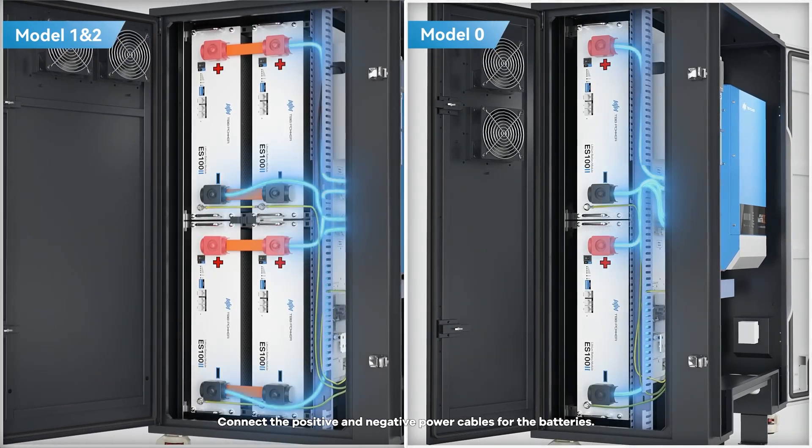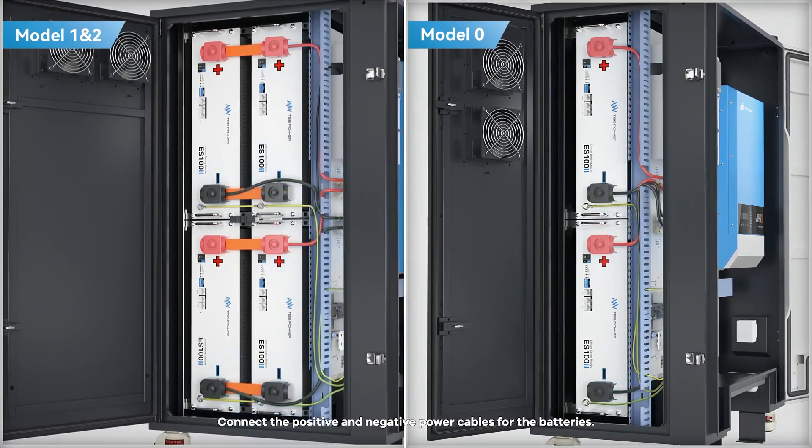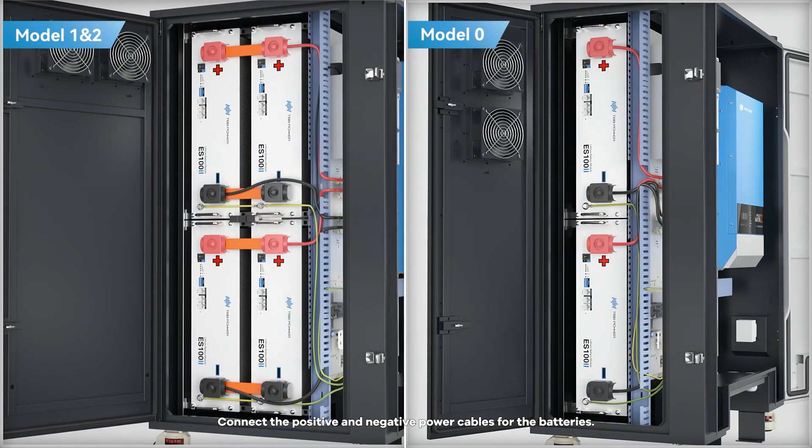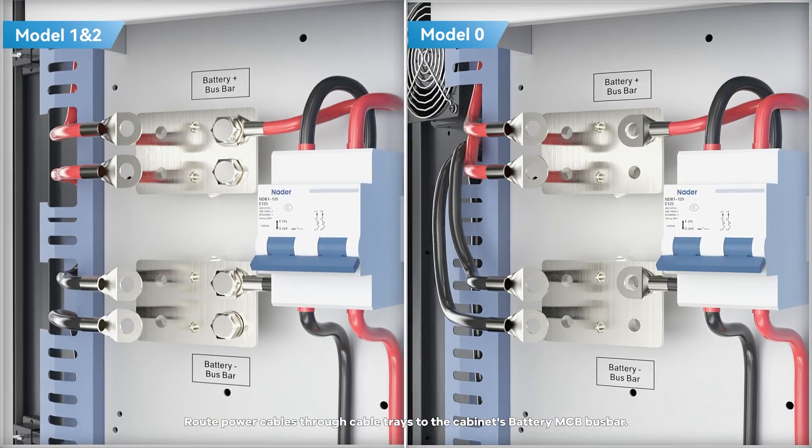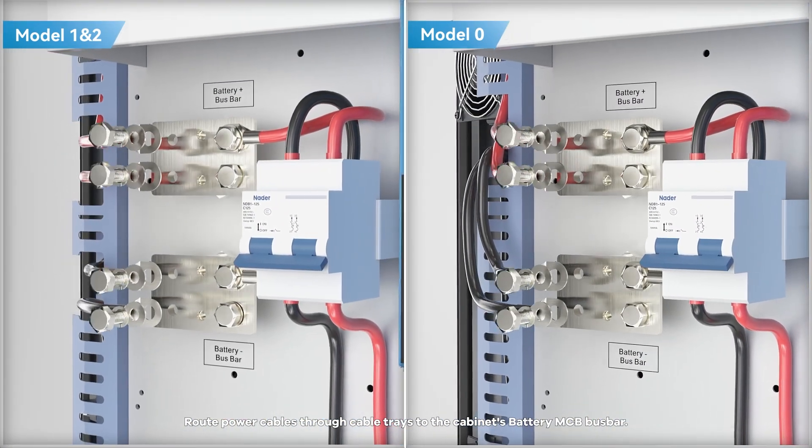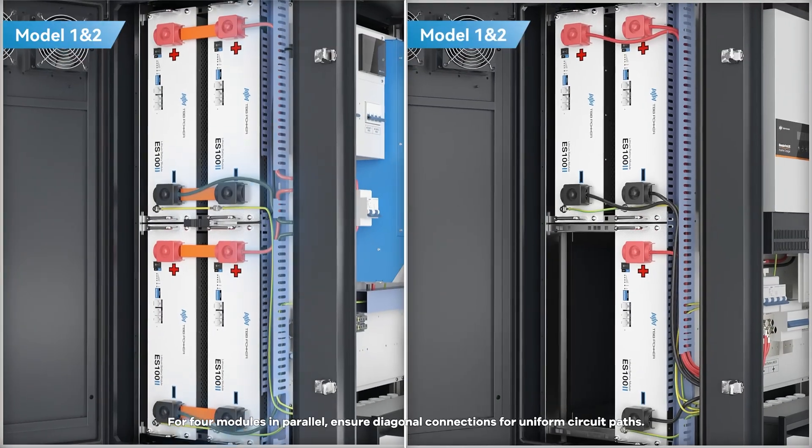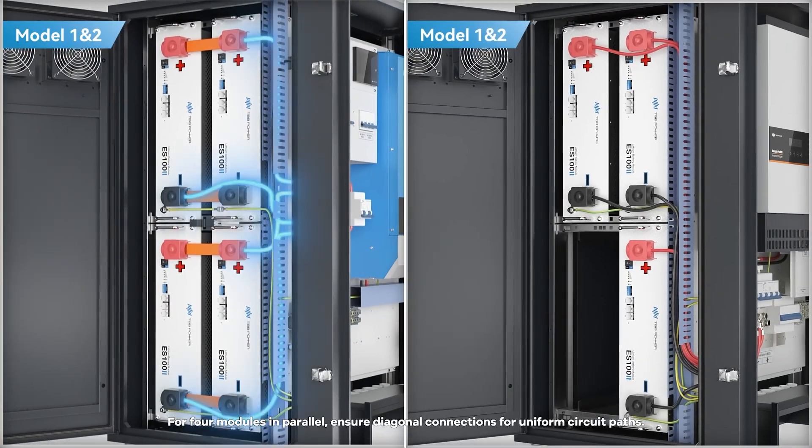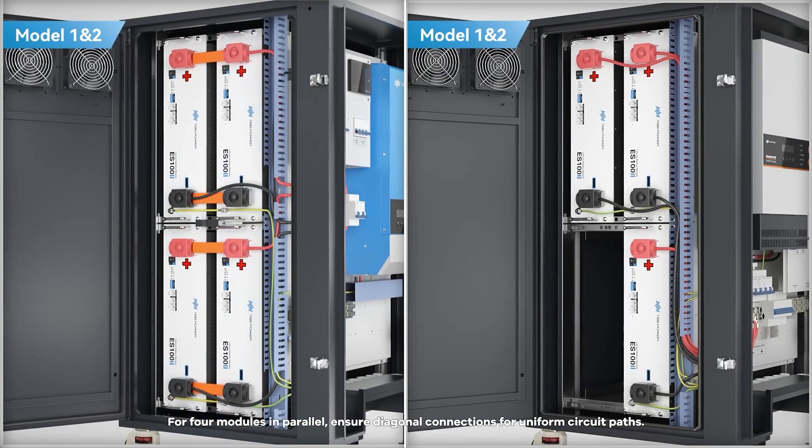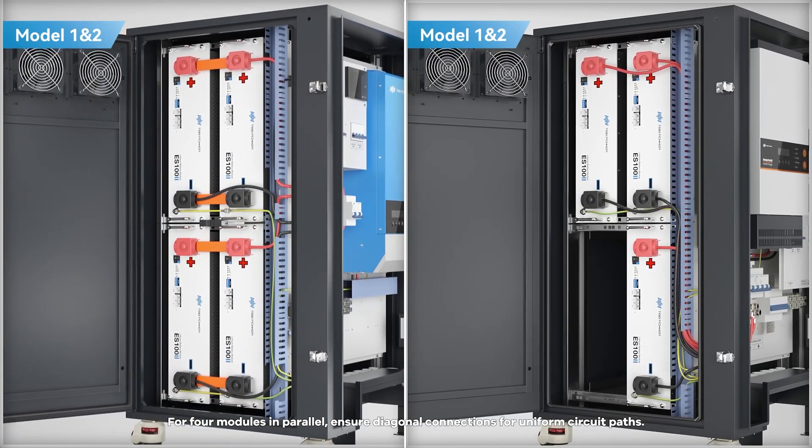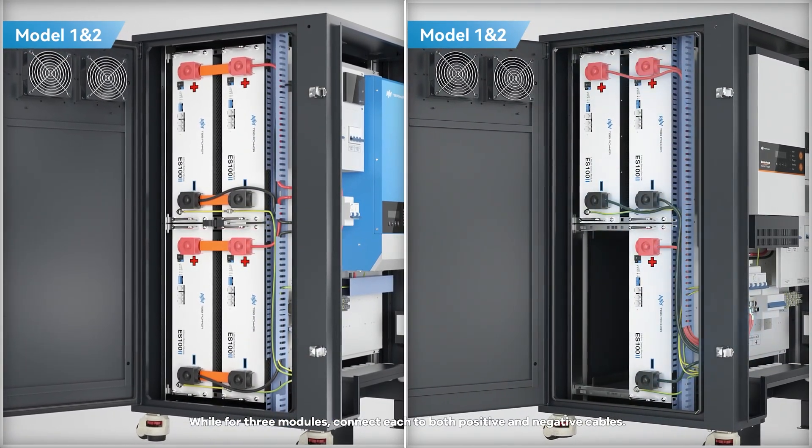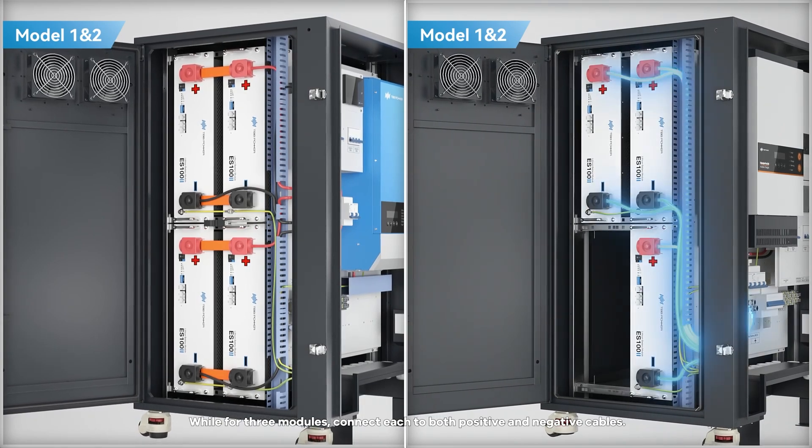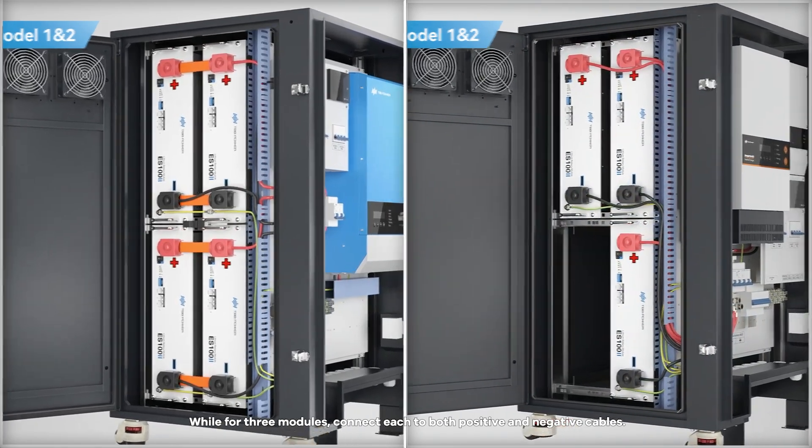Connect the positive and negative power cables for the batteries. Route power cables through cable trays to the cabinet's battery MCB bus bar. For 4 modules in parallel, ensure diagonal connections for uniform circuit paths. While for 3 modules, connect each to both positive and negative cables.